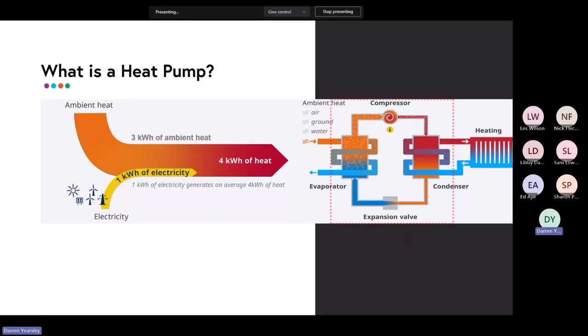So when you're coming from a boiler background, typically you'll supply it, let's say, 1 kilowatt worth of natural gas or diesel, and the boiler will combust that, turning that into 990 watts of heat if it was 99% efficient, or at some sort of rate of efficiency. And when you have an air-to-water heat pump, that's not what happens.